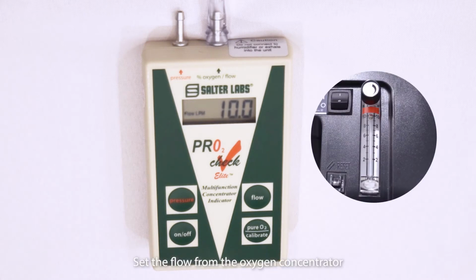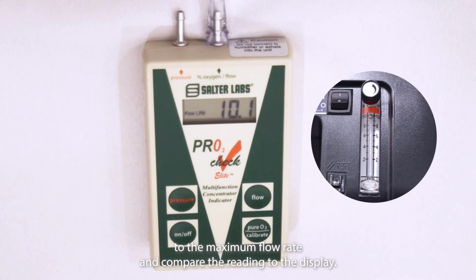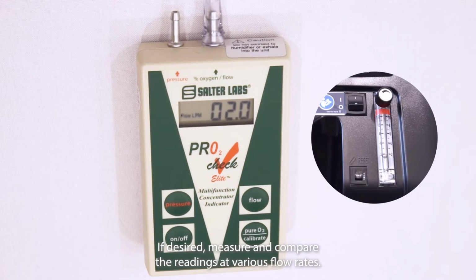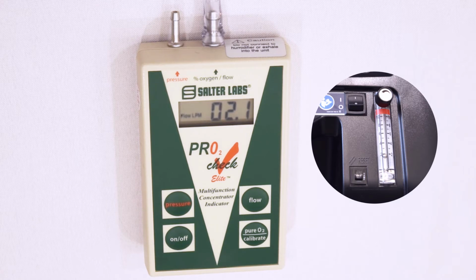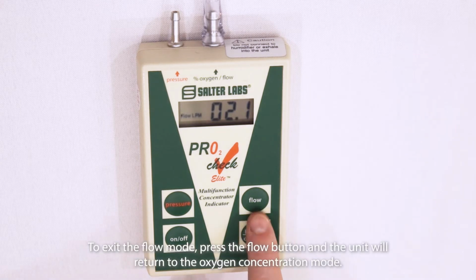Set the flow from the oxygen concentrator to the maximum flow rate and compare the reading to the display. If desired, measure and compare the readings at various flow rates. To exit the flow mode, press the Flow button and the unit will return to the oxygen concentration mode.